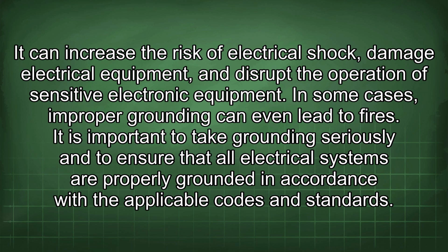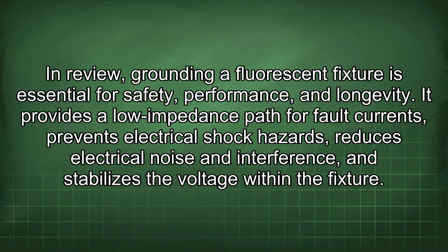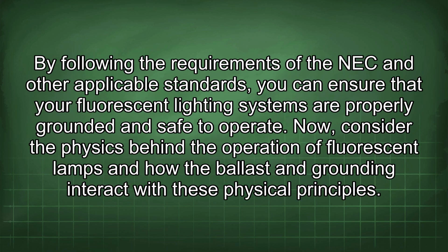It is important to take grounding seriously and to ensure that all electrical systems are properly grounded in accordance with the applicable codes and standards. In review, grounding a fluorescent fixture is essential for safety, performance, and longevity. It provides a low impedance path for fault currents, prevents electrical shock hazards, reduces electrical noise and interference, and stabilizes the voltage within the fixture. By following the requirements of the NEC and other applicable standards, you can ensure that your fluorescent lighting systems are properly grounded and safe to operate.